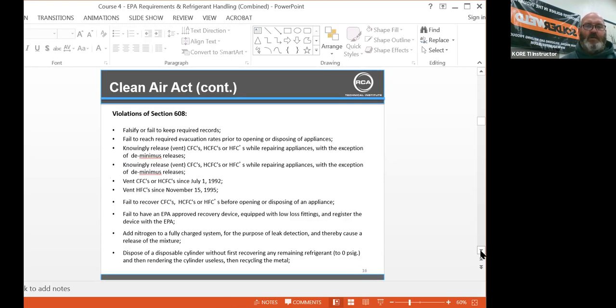Violations of the 608: falsify or fail to keep required records, fail to reach required evacuation rates prior to opening or disposing of an appliance, knowingly releasing or venting HCFCs, CFCs, or HFCs while repairing appliances, with the exception of de minimis release. De minimis is just what comes out of your hoses, things like that.